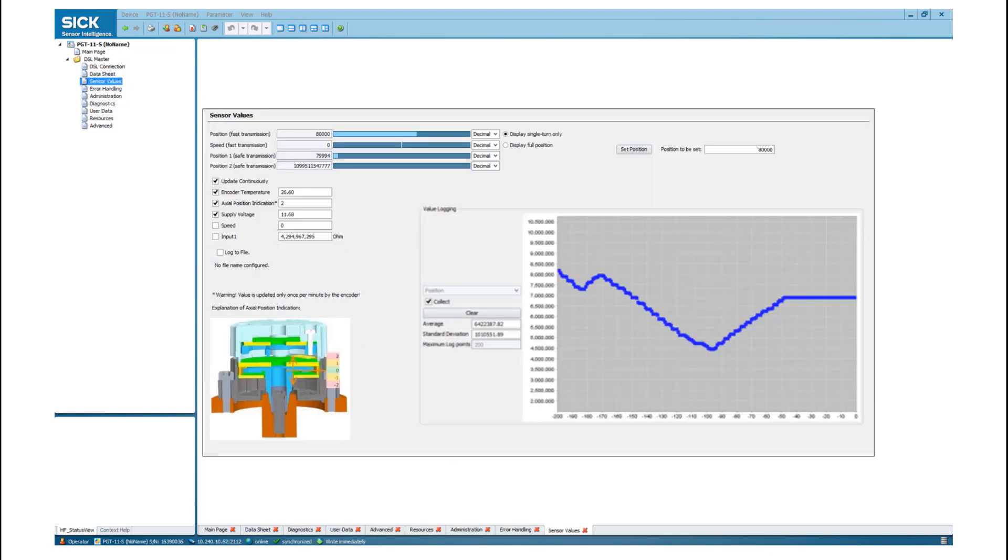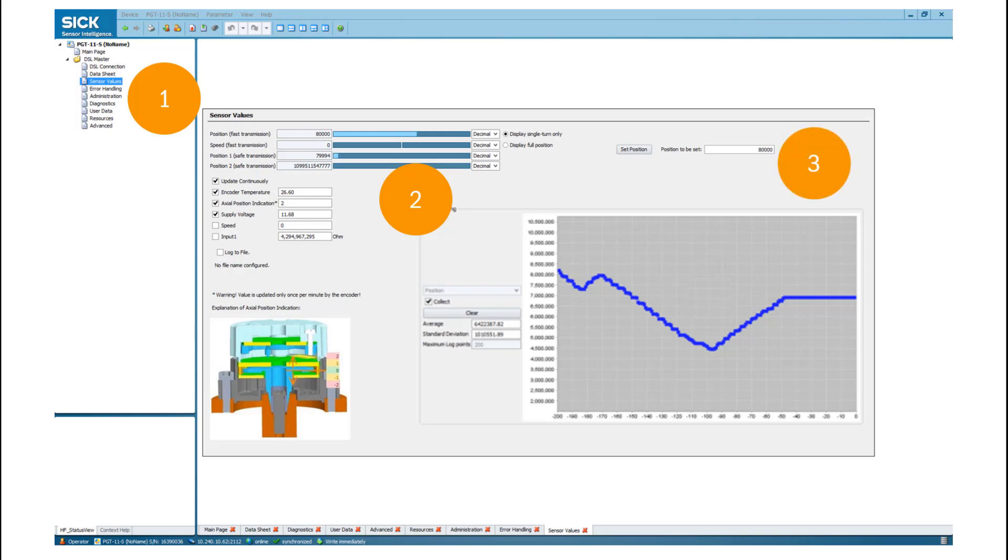In the sensor values tab, you can see and record the actual measurement data. The actual absolute position and the actual speed are displayed on the upper left side of the window. During commissioning of the servo motor, it is required to align the mechanical position of the motor shaft with the electrical position value of the sensor. Therefore, you can enter the desired position value, for example zero, in the box. By activating the set position button, the new value will be displayed and is assigned to the encoder.